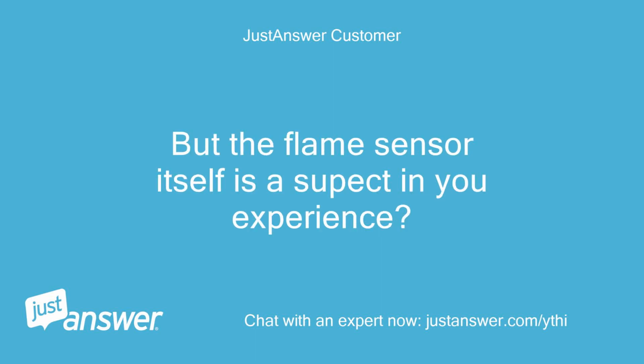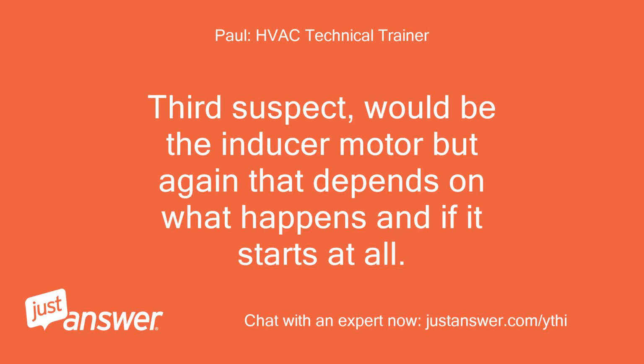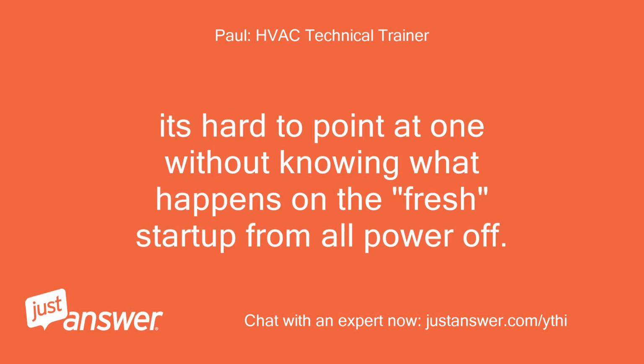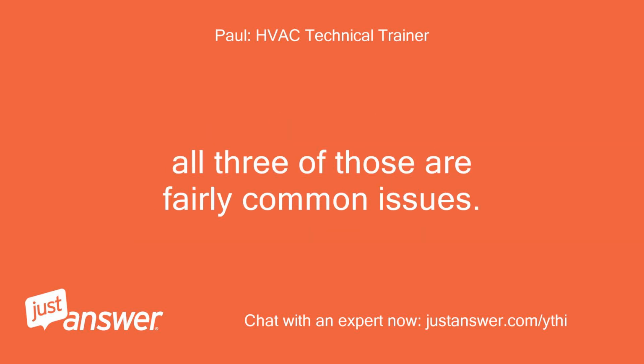But the flame sensor itself is a suspect in your experience? Third suspect would be the inducer motor, but again that depends on what happens and if it starts at all. It's hard to point at one without knowing what happens on the fresh startup from all power off. All 3 of those are fairly common issues.